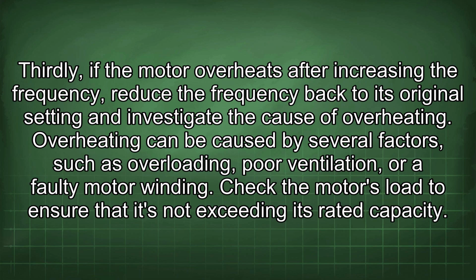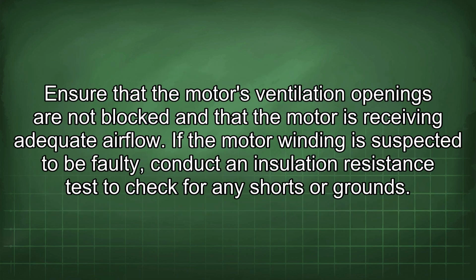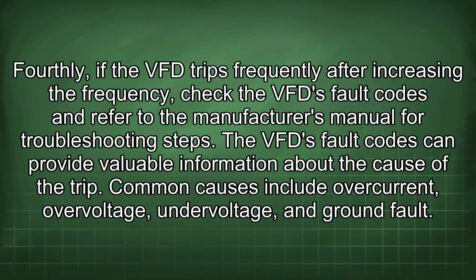Overheating can be caused by several factors, such as overloading, poor ventilation, or faulty motor winding. Check the motor's load to ensure that it's not exceeding its rated capacity. Ensure that the motor's ventilation openings are not blocked and that the motor is receiving adequate airflow. If the motor winding is suspected to be faulty, conduct an insulation resistance test to check for any shorts or grounds.